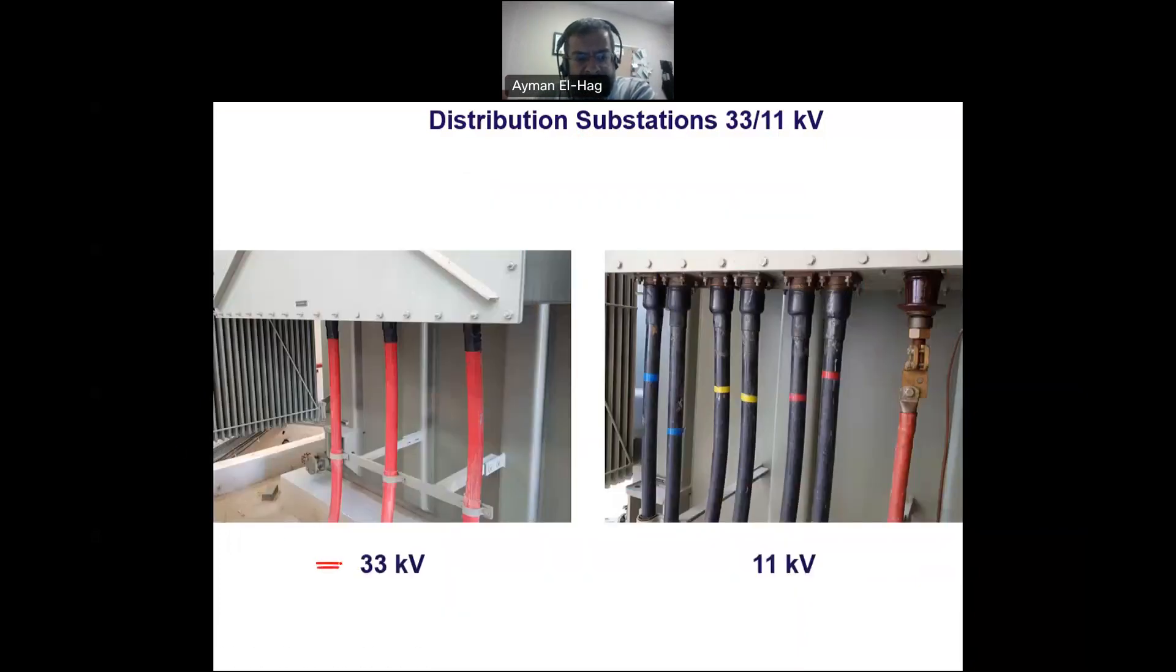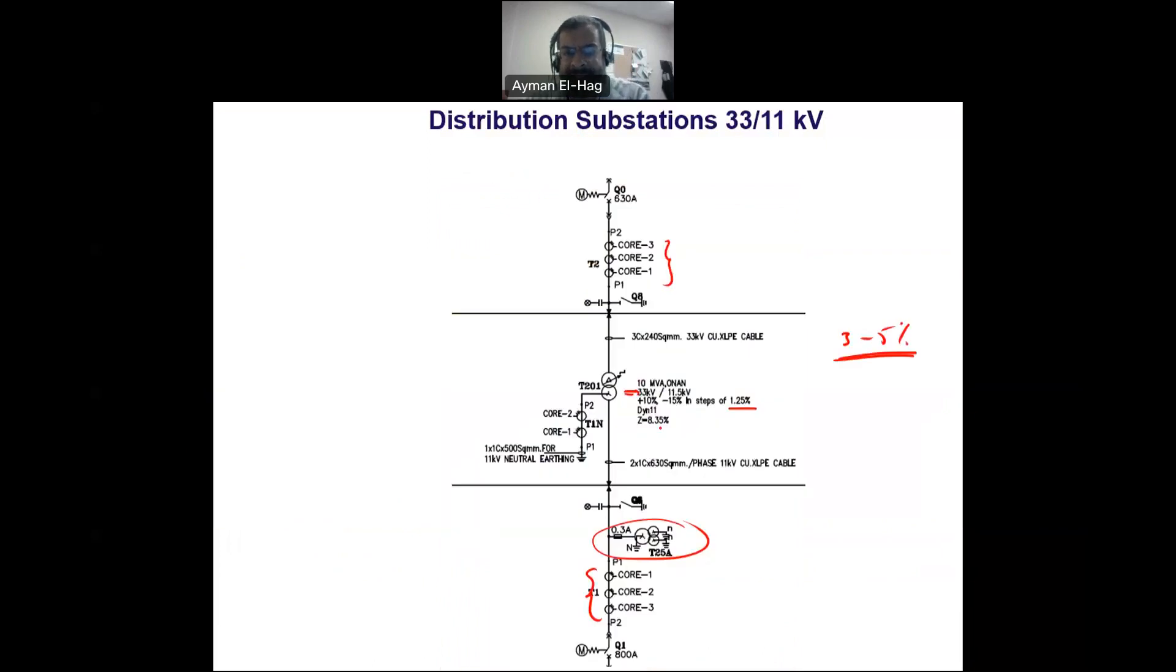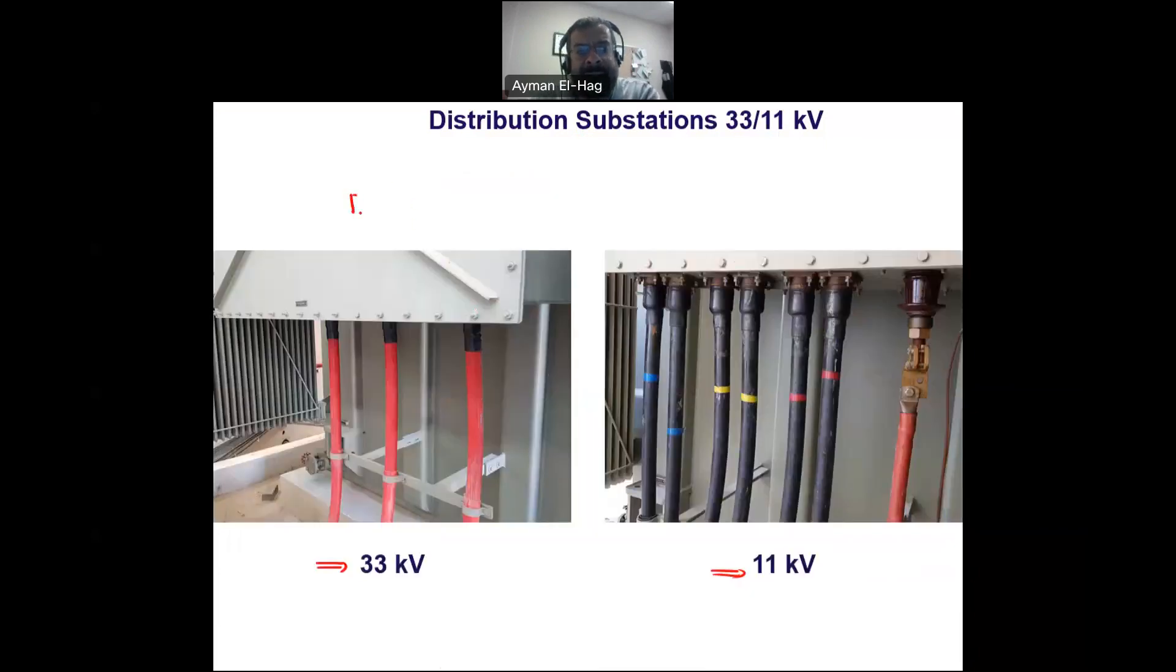This is the high voltage side, and this is the low voltage side. The transformer is Dyn11. At the high voltage side, it's connected as delta, and at the low voltage side, it's connected as wye with neutral. In the delta, we need only three conductors. These are the three conductors at the high voltage side, but for the low voltage side, we need four conductors, three for the three phases and one for the neutral.